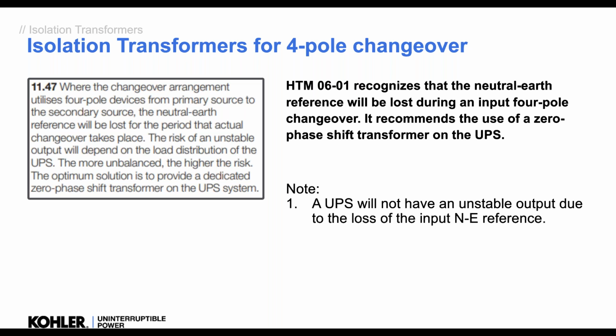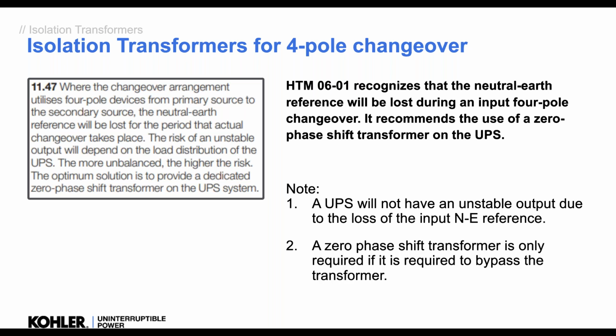Okay. Well, the UPS will not become unstable just because we lose a neutral earth reference. If we lose 3 phase and neutral on the input of the UPS, the output of the UPS will remain fine, stable, 230 volts line to neutral, 400 volts line to line, but we have got no neutral earth reference. So the neutral earth will be floating. Okay. A 0 phase shift transformer is optimum because it creates no phase shift between input and output, and it means we can put a bypass around it if we need to. A normal isolation transformer will have a 30 degrees phase shift.